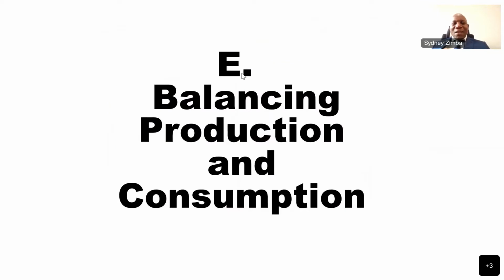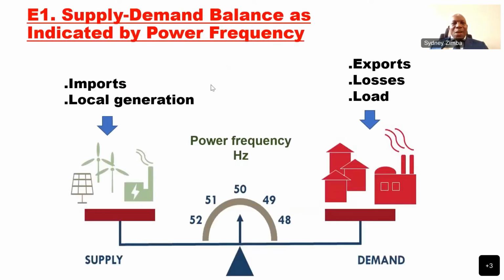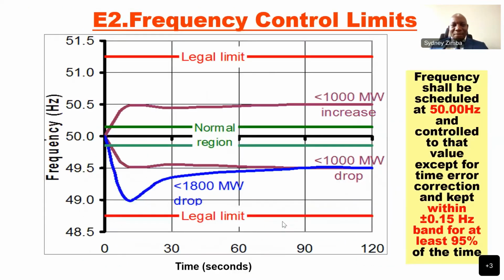Okay, so the second one, second from last, is the balancing of production and consumption. This is the one which is talking about the reserves. Of course, you have to balance the supply and demand. And our indicator is the power frequency. At nominal it is 50 hertz. Imports and local generation on the left. On the right, we've got the exports, losses, and load. When they balance, your frequency is around 50 hertz.